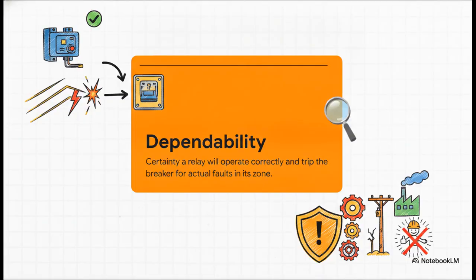So let's put some formal names to these two sides. First up, dependability. This is the absolute certainty a relay will operate correctly and trip the breaker for every actual fault within its designated zone. When you prioritize dependability, you're basically saying, I absolutely cannot afford to miss a fault. Missing one is a dependability failure, leading to ruined infrastructure and severe safety hazards.